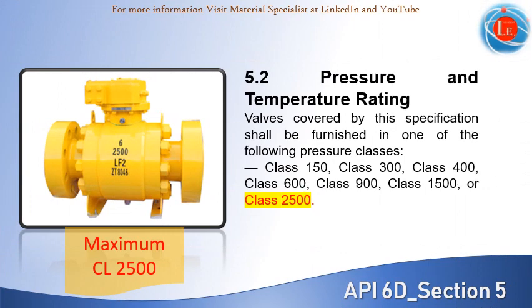Pressure rating designation is the word 'class' followed by a dimensionless number, which is the designation for pressure-temperature ratings. Valves covered by API 6D specifications shall be furnished in one of the specified pressure classes; however, it is not applicable to valves having pressure ratings exceeding class 2500.